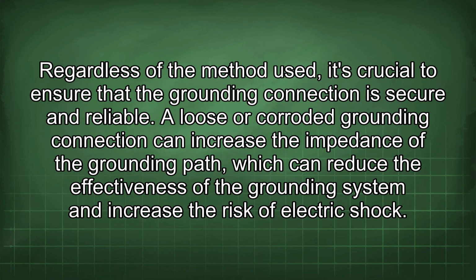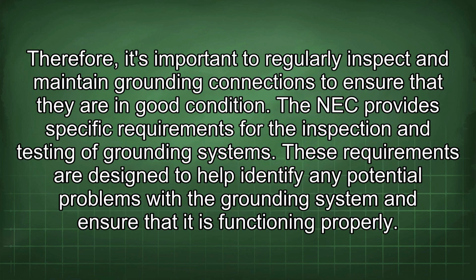Regardless of the method used, it's crucial to ensure that the grounding connection is secure and reliable. A loose or corroded grounding connection can increase the impedance of the grounding path, which can reduce the effectiveness of the grounding system and increase the risk of electric shock. Therefore, it's important to regularly inspect and maintain grounding connections to ensure that they are in good condition. The NEC provides specific requirements for the inspection and testing of grounding systems.